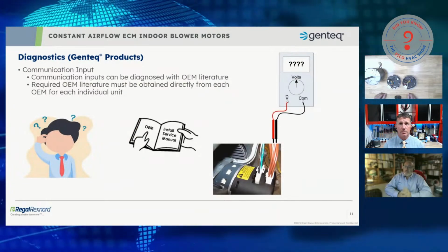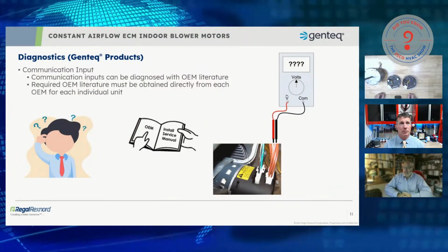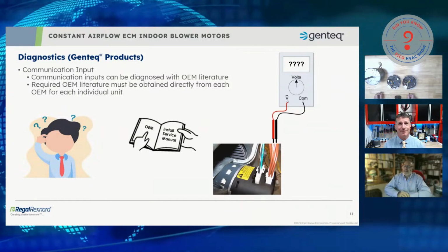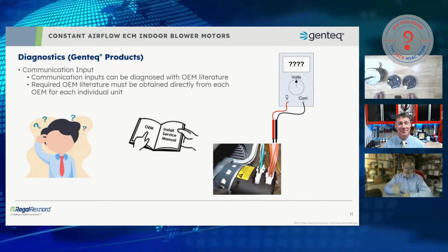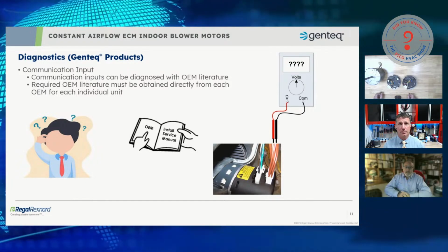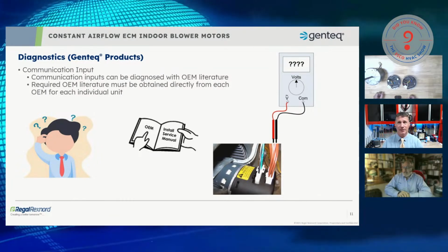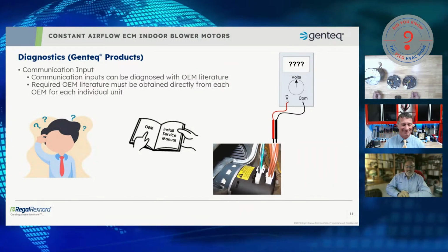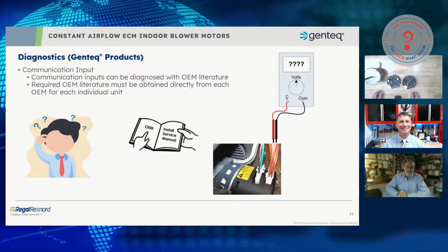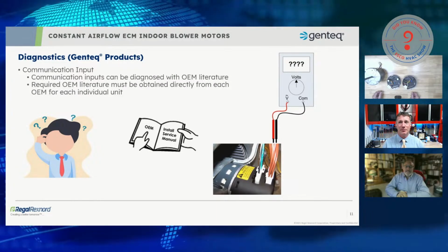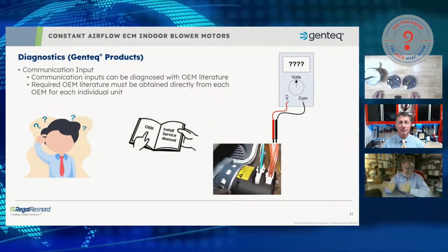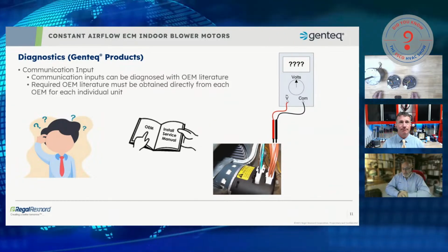Right. And I love this picture because it is an actual picture. If I'm being honest, it's my furnace in my home. And I have a 16-pin motor with 16 brown wires. And if you look, they're not numbered, they're not color-coded, and on the schematic, there's 16 black lines that have no reference for voltage. Absolutely. So can you diagnose a motor without buying a special tool?